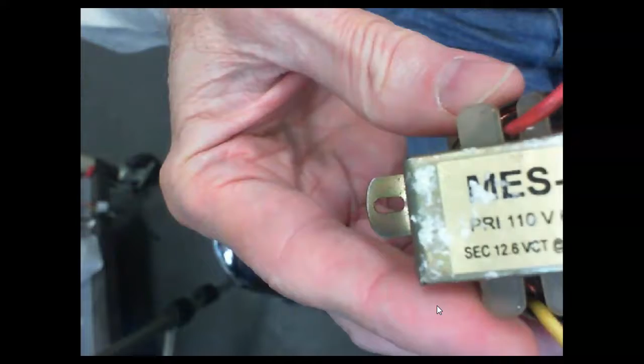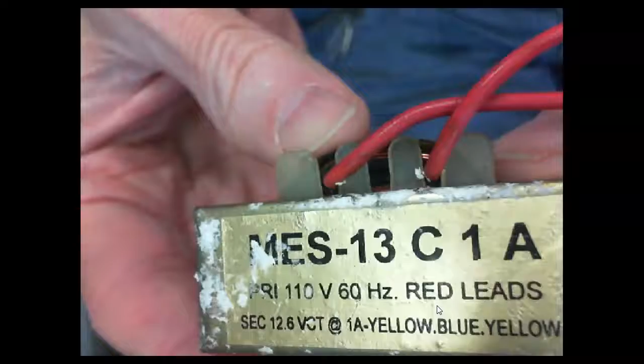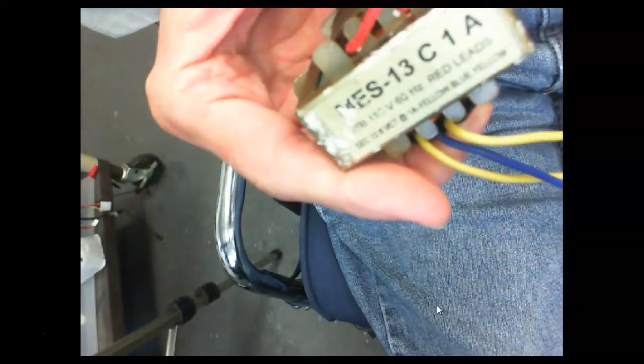Our transformer is sealed inside the trainer, but y'all need to know it's not labeled right - that's the biggest problem. It's labeled 6.3, 6.3, 0, but you'll never find a transformer labeled like that. This is a transformer, and this is the actual label on it: 110 volts, 60 hertz, red lead, secondary 12.6 VCT. So we think VCT, center tap transformer, but it doesn't say 6.3 and it doesn't say 0 on the center tap. It's whatever you make it to be, right? So I don't like the way the trainer is labeled.